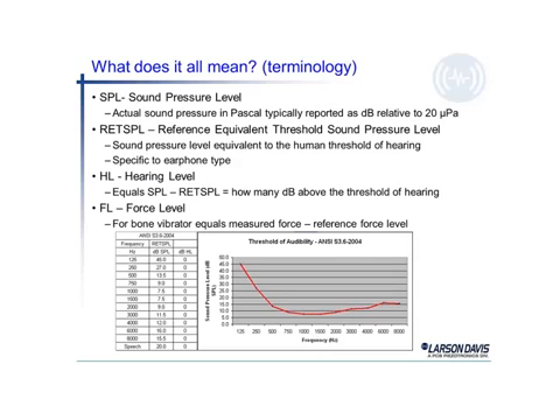Terminology, what does it all mean? The sound pressure level, abbreviated as SPL, is an actual sound pressure in units of Pascal, and this is typically reported as dB. It's relative to 20 micropascal, which happens to be the threshold of hearing. The RETSPL, the reference equivalent threshold sound pressure level, equates the sound to this human threshold of hearing, an average human, by the way, if there is such a thing, and then specific to an earphone type.